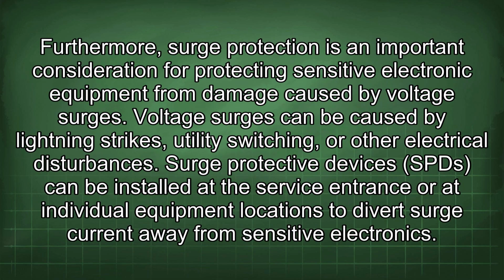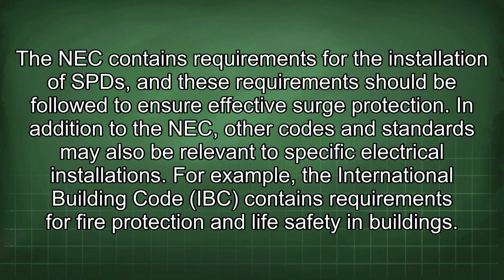Furthermore, surge protection is an important consideration for protecting sensitive electronic equipment from damage caused by voltage surges. Voltage surges can be caused by lightning strikes, utility switching, or other electrical disturbances. Surge protective devices (SPD) can be installed at the service entrance or at individual equipment locations to divert surge current away from sensitive electronics. The NEC contains requirements for the installation of SPD, and these requirements should be followed to ensure effective surge protection.